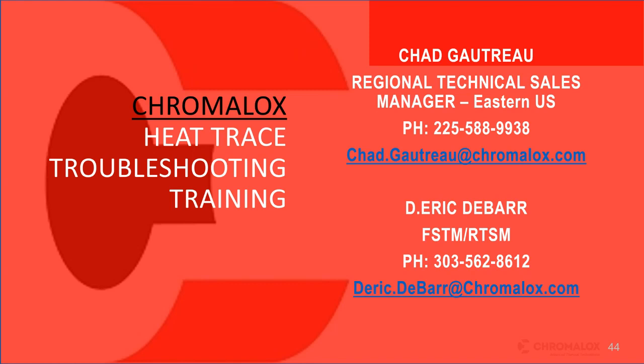Okay, yeah, we're getting a lot of questions here, Chad. Please define ground fault protection and how it relates to heat tracing. So the National Electric Code, I believe in 1987, required a change in ground fault protection, and each individual circuit has to have ground fault protection now. So you either have to provide ground fault protection through the use of a ground fault breaker, or you have to provide it in your controller. It's basically protecting, just like any other circuit. If we detect a ground fault, it's going to trip the breaker and not allow the cable to sit there and arc and spark and start a fire. So those are the two ways that you can accomplish it. But it is required by code, and if you don't have it on your current system, I would advise that you install ground fault breakers.